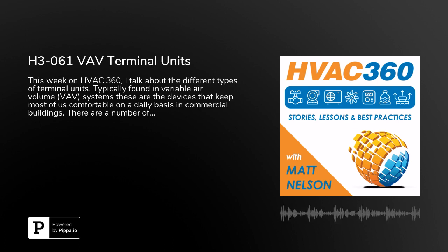The one thing about the series powered boxes is not only does it have the fan on the discharge side, but the fan will always be on. So when the unit's on, the fan's on, which I'll make mention of in a little bit as to why that's important. As far as adding on supplemental heat like electric reheat or a hot water heating coil, that's all going to be downstream of the box, on the discharge of the box. So you have the fan blowing straight into the electric coil or the hot water coil.